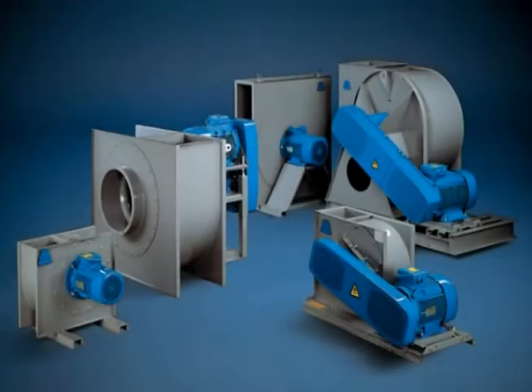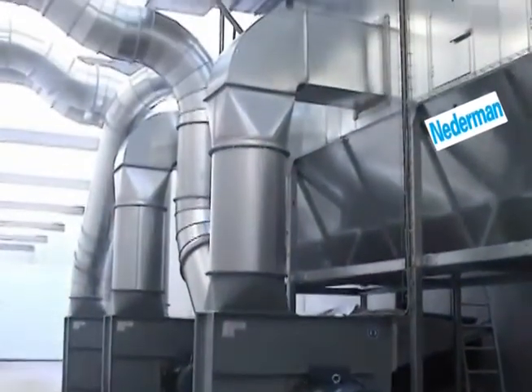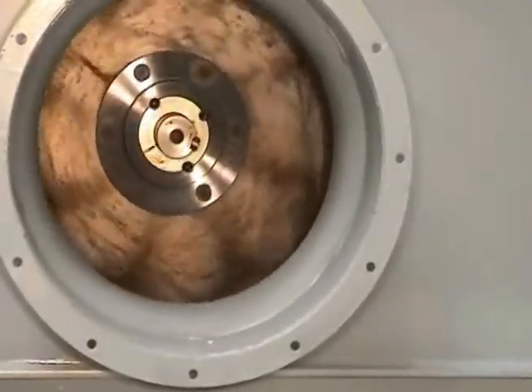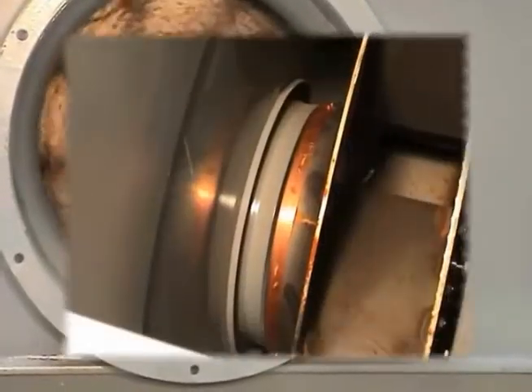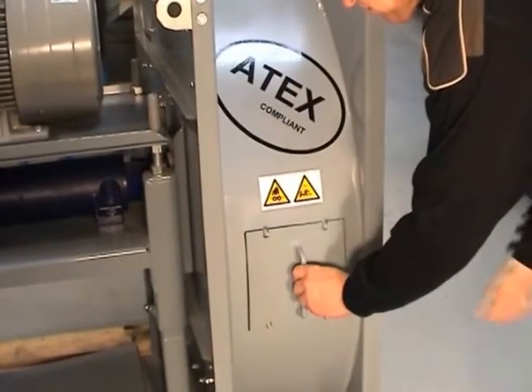The fan is an important part of the system. The relatively high pressure levels call for a special fan design to avoid ignition sources. The air movement is created by the rotating impeller. The distance between the rotating impeller and the stationary fan housing shall exceed certain limits and shall be controllable.